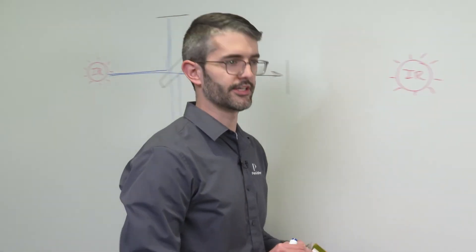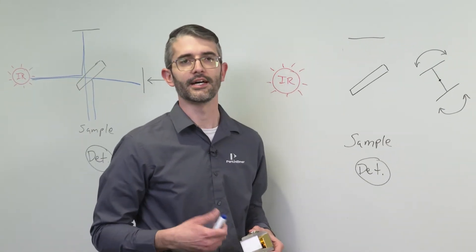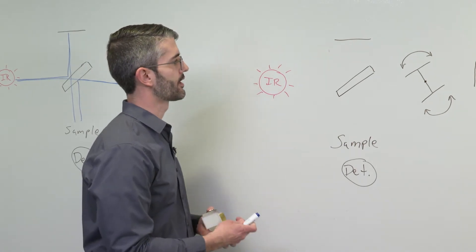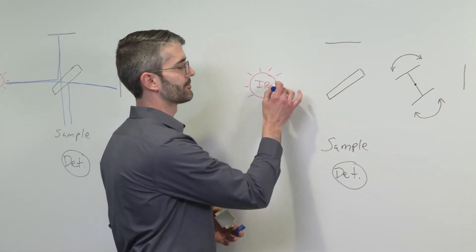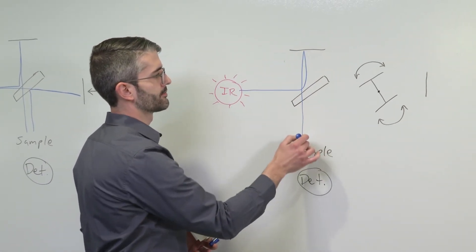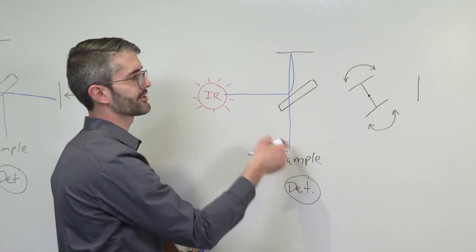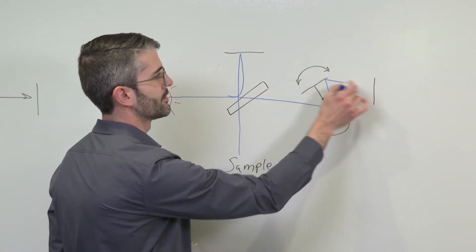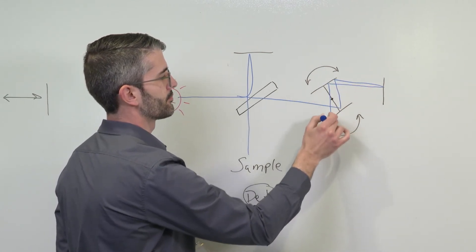For some years now, PerkinElmer has employed what is known as the Dynascan interferometer. In the Dynascan interferometer, the infrared light comes from the infrared source to the beam splitter, off the fixed mirror, and a portion of that light also travels through the pivoting mirror pair.